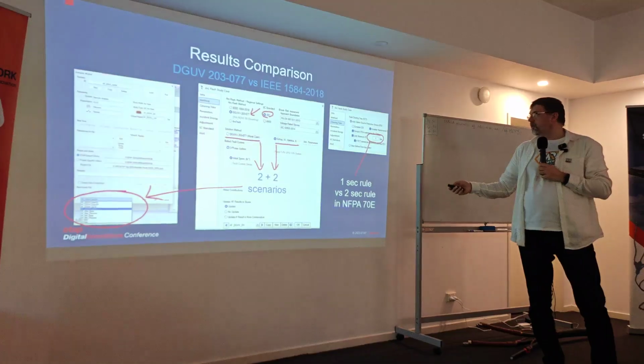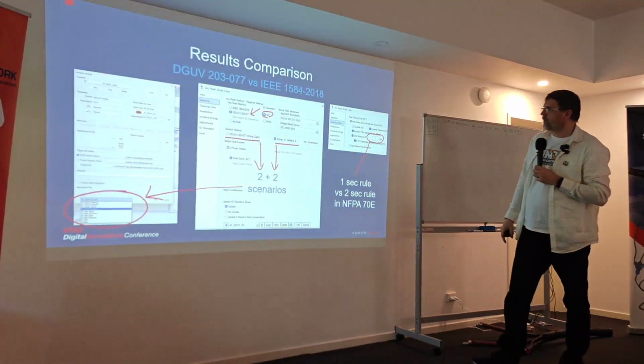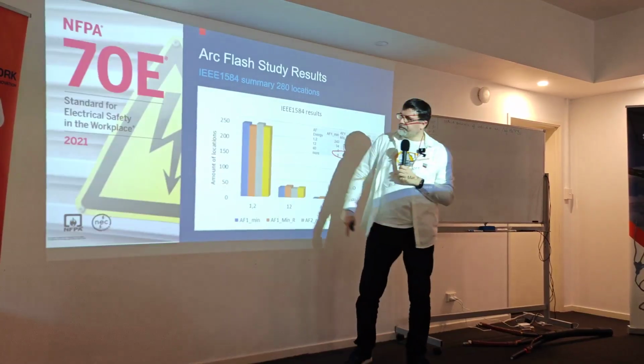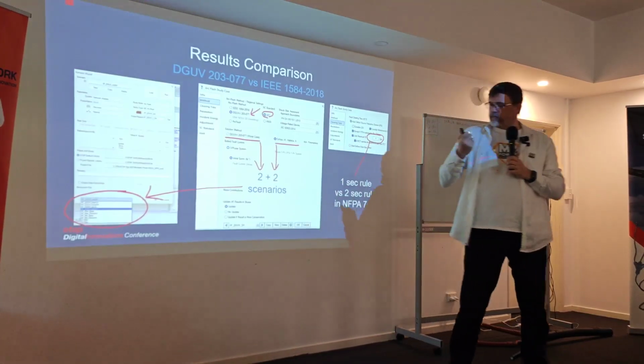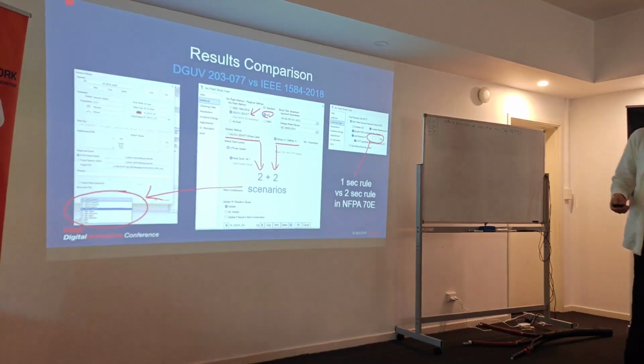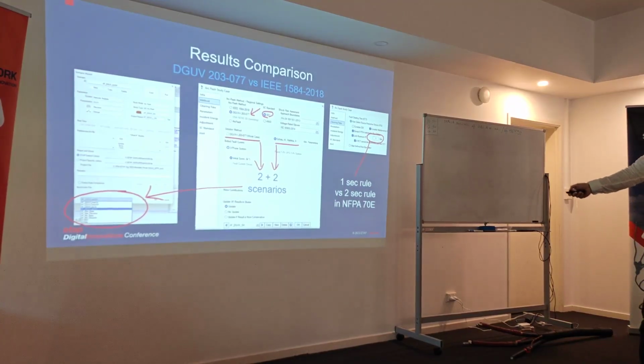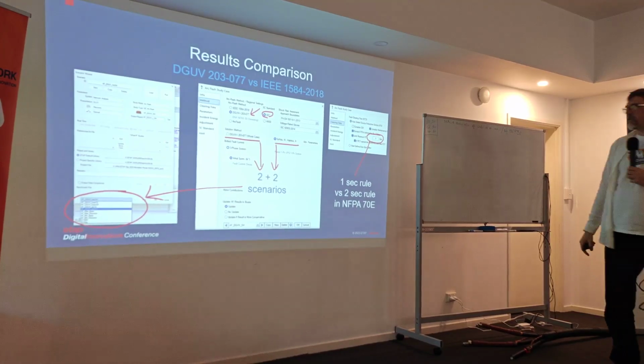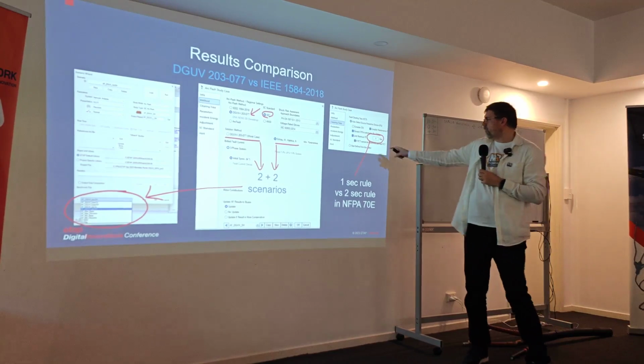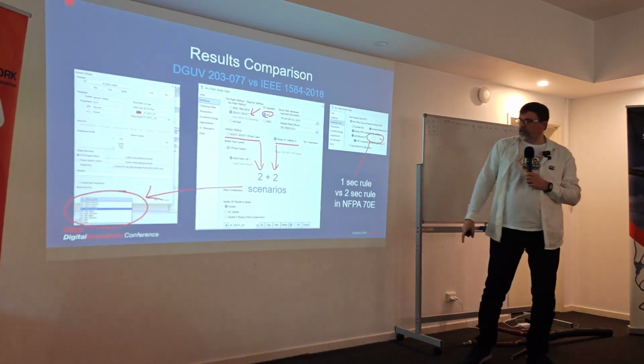And then you don't have to look at this, but there was some configuration done for the DGUV calculations, and then for the IEEE calculations. That was for the software people, yeah? And the main issue was that I modified a few things based on the 1 second rule, not the 2 second rule that ETAP has.